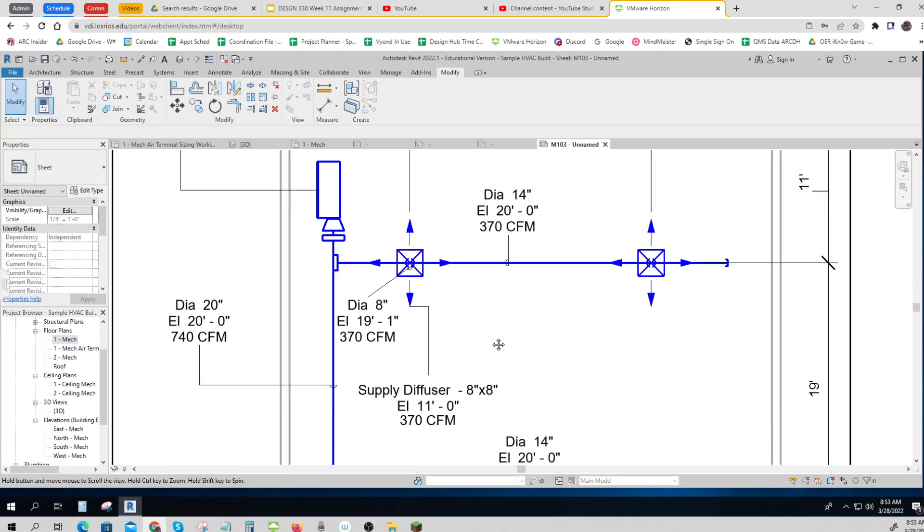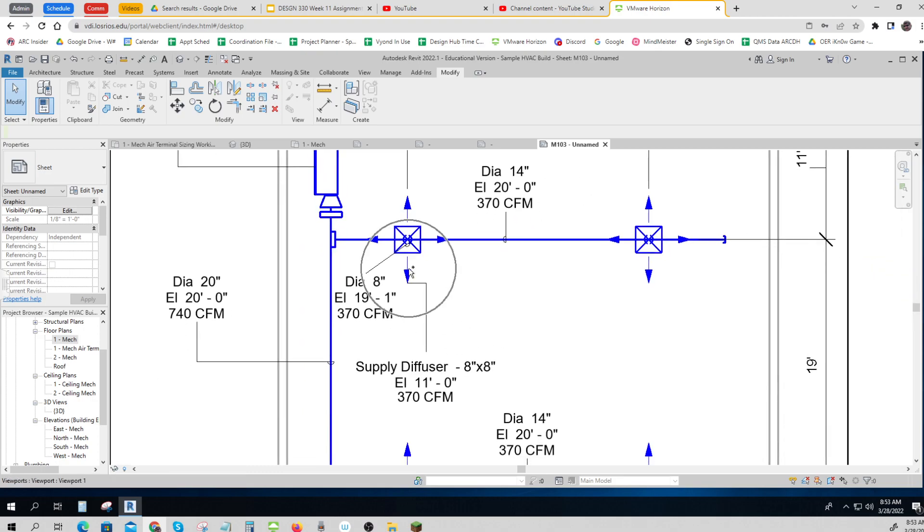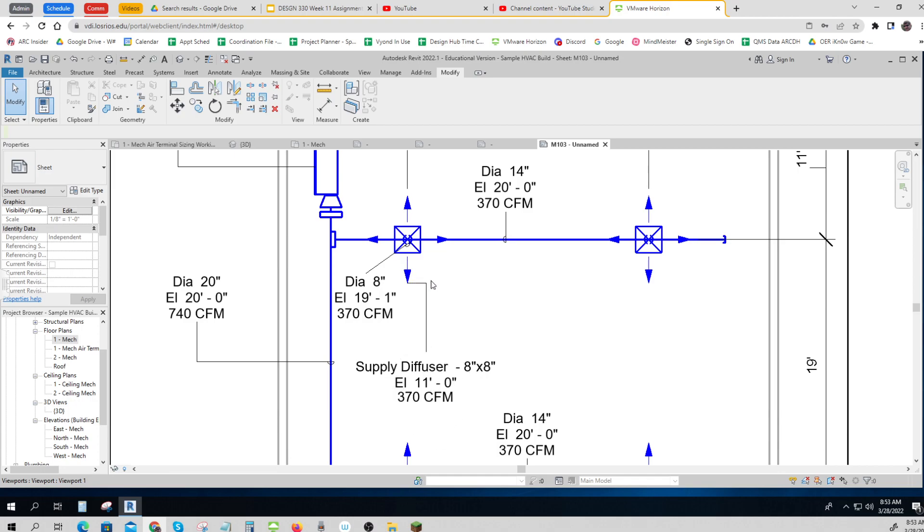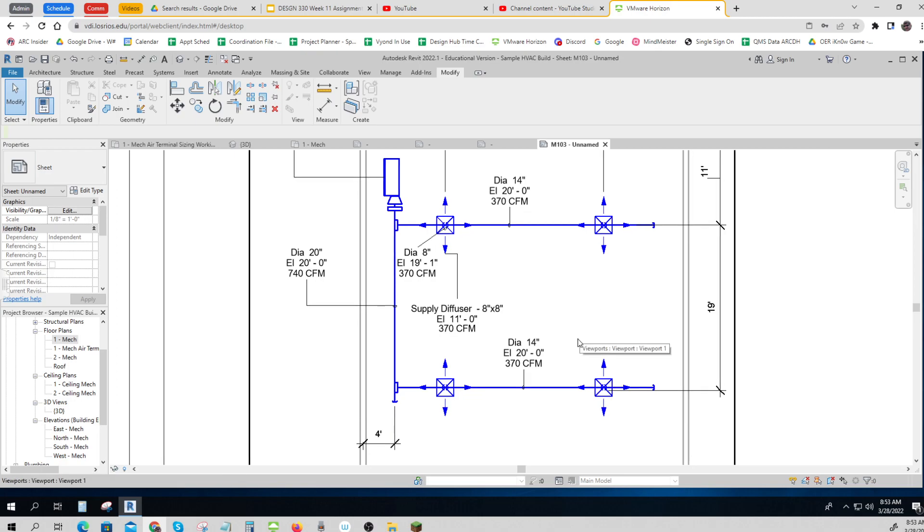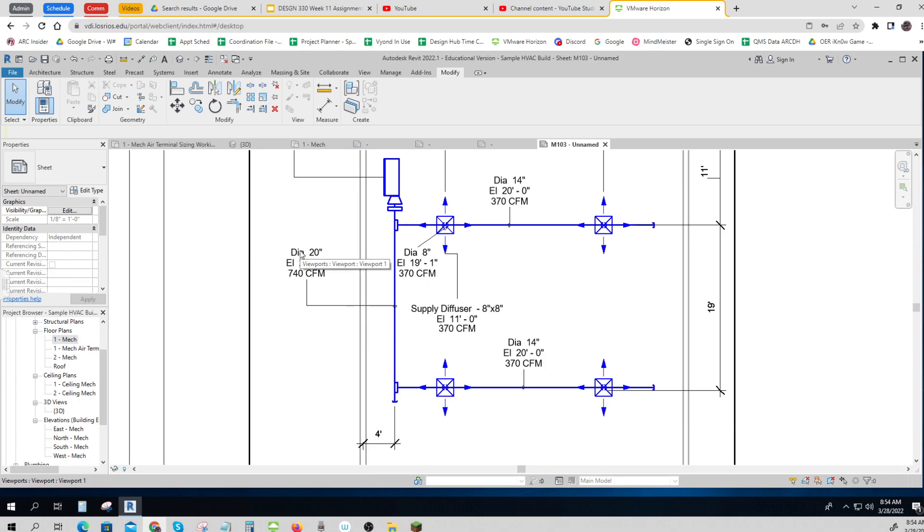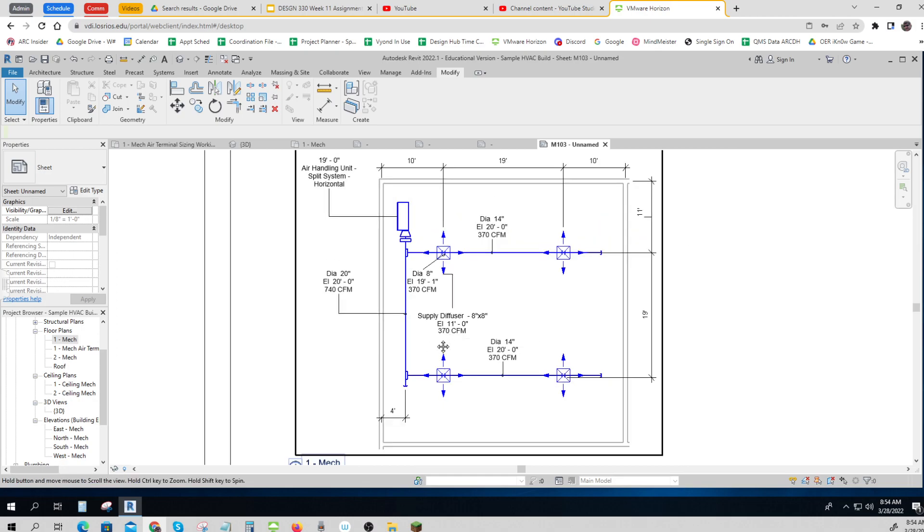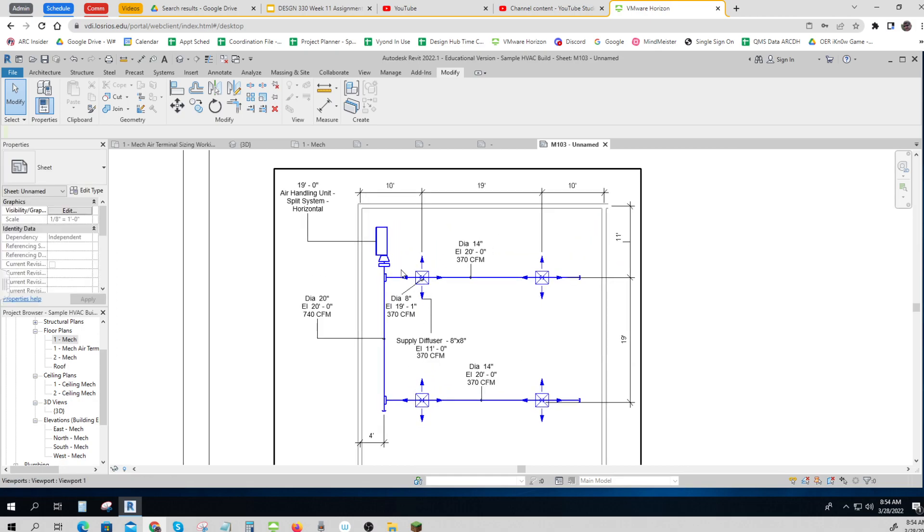And then we've got our diffuser, which I'm saying it's a supply. It's an 8x8 duct, and it's at 11 feet, and it's going to do 370 CFM. And I'm only pointing to one of them. And then this one over here has 740 in it going through it, 740 CFM, and it's 20-inch ducting at 20. So that's what you want on your labels. And then I also have my mechanical unit here.